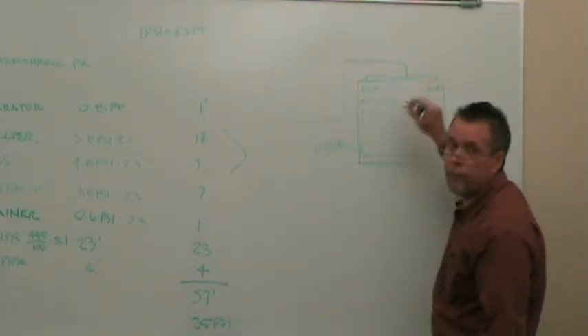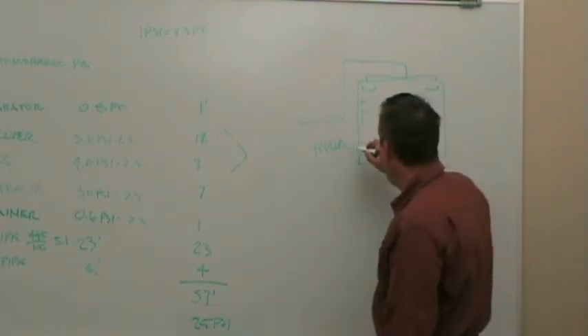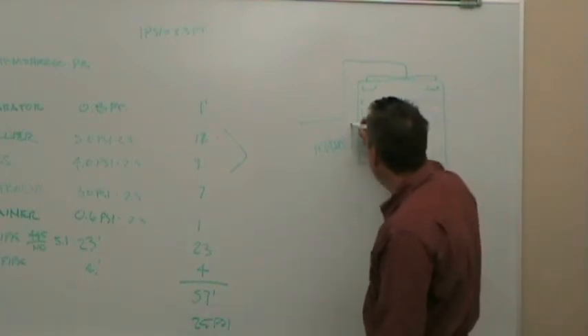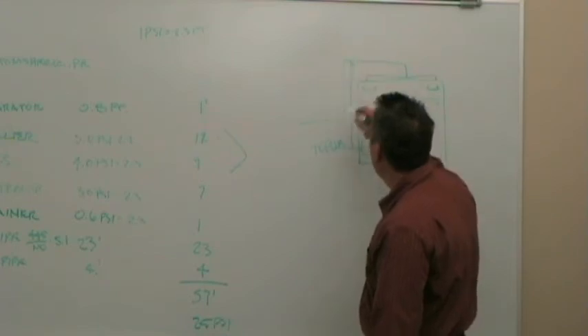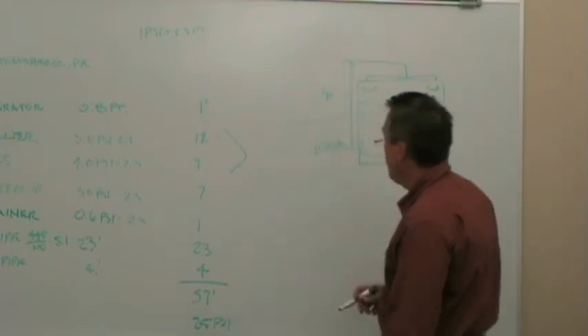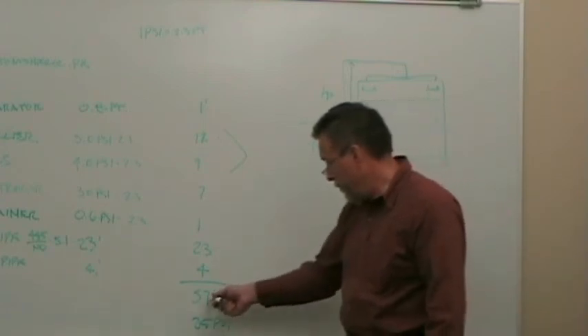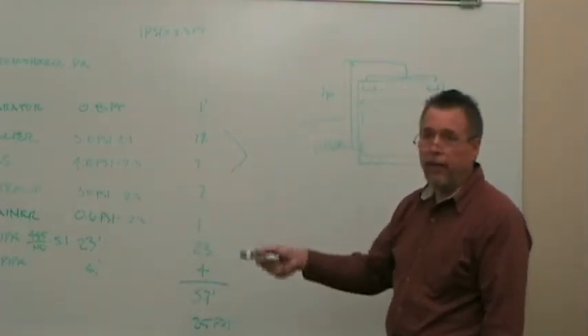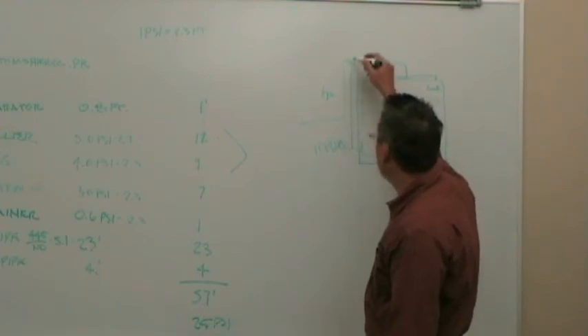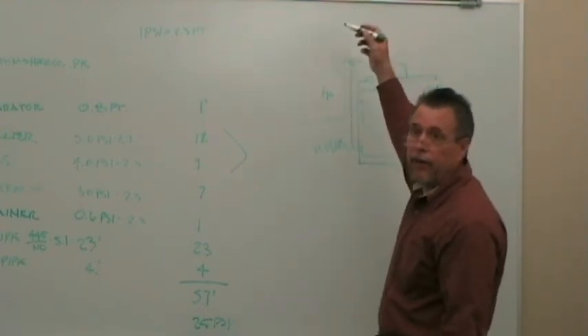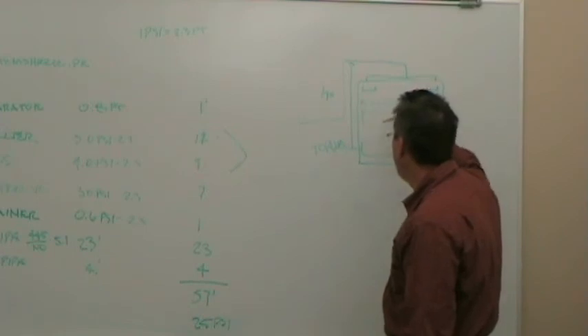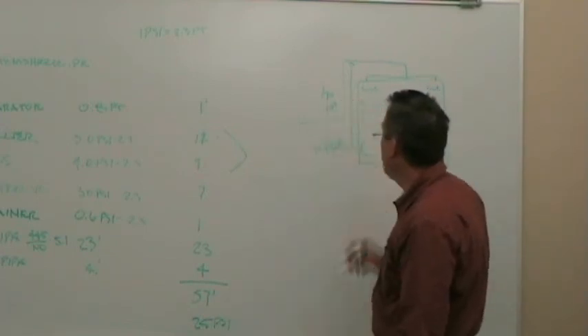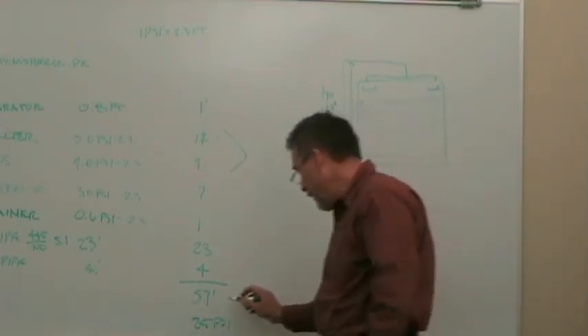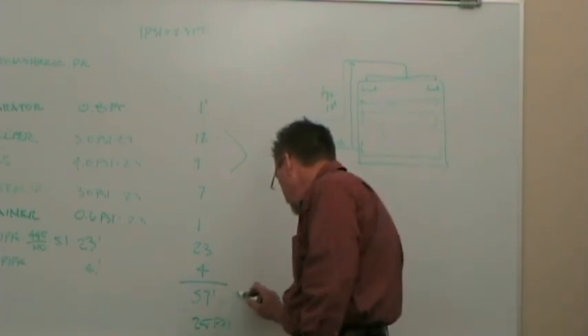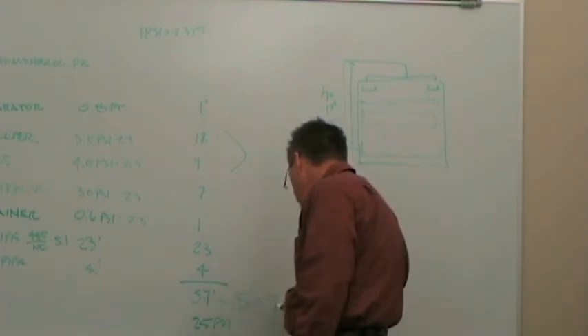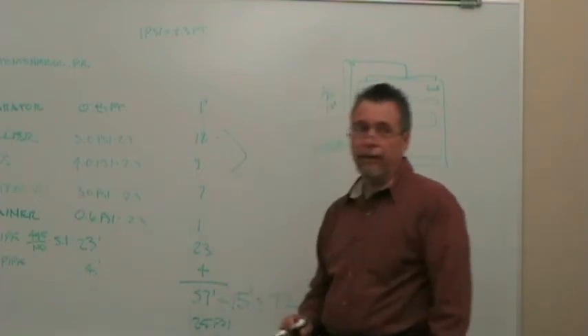Well, this is open, right? So now I've got to compensate for lifting that pipe up. There's H, that right there. So when I calculate my pressure loss through my pipe and fittings, this is an actual lift. Then I've got to lift that water up because it's open inside here, so that cooling tower is 15 feet tall.